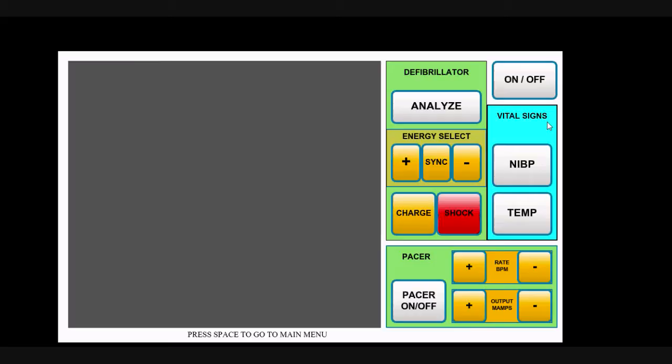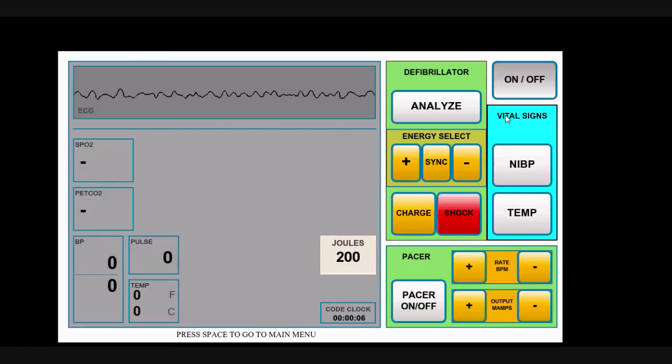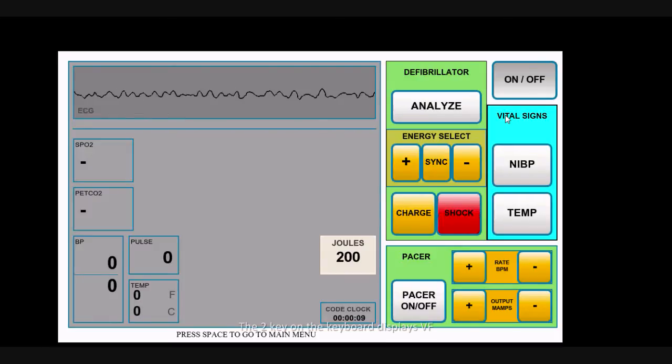Let's say that you have the tablet in your station, the software is loaded as you see here. I'll be using the mouse to simulate the student's finger. The student hits the on-off key, applies the electrodes to the patient, and you decide you're going to give them a lethal ventricular arrhythmia. By hitting two, you're going to throw up some ventricular fibrillation.